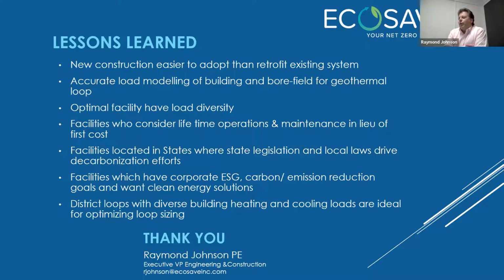Here are things I'd recommend, things we've learned, and I've got to qualify a few of these. New construction is easier to adopt than retrofit of an existing system - that's not necessarily true, but if you have a site that can support a bore field outside of the building envelope, outside the footprint of the building, that helps. What we had was a building from the ground up, so we had to use the footprint of the building for a bore field. It's important, especially in New York where buildings are so dense, that you've got the site.